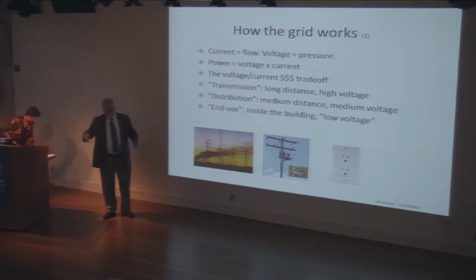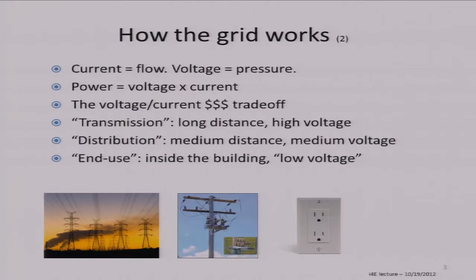But now we're talking about smaller systems, pieces of wood this long instead of pieces of steel all the way across this room. It's less expensive, but the losses are higher for a given amount of energy because we're only at 24,000 volts, so you need more current. You still don't want to bring 24,000 volts into your house, so before it gets there, it's stepped down one more time to 120 or 240 volts, which is where you use it. You don't want to move that voltage level more than 100 meters or so, or you get tremendous losses from the current.